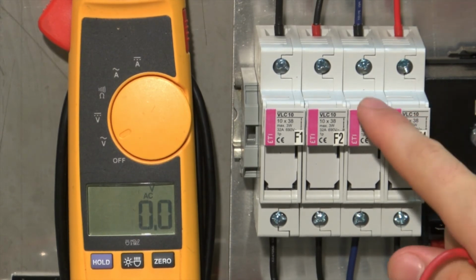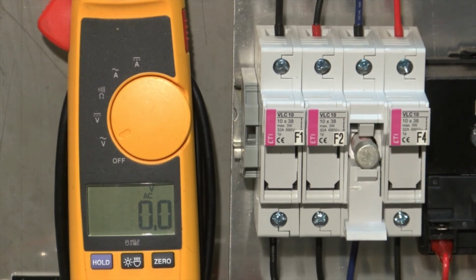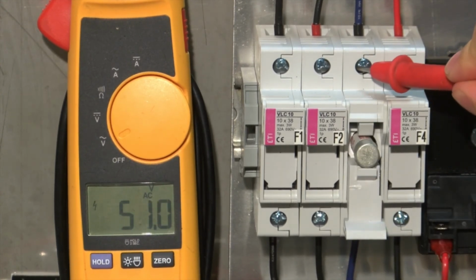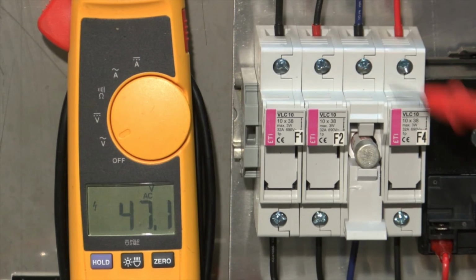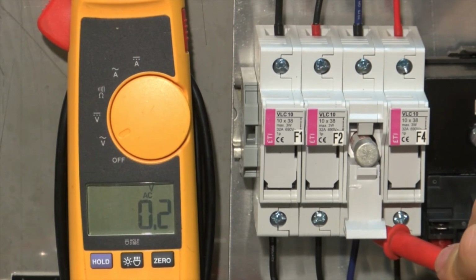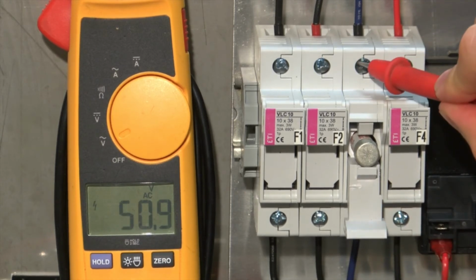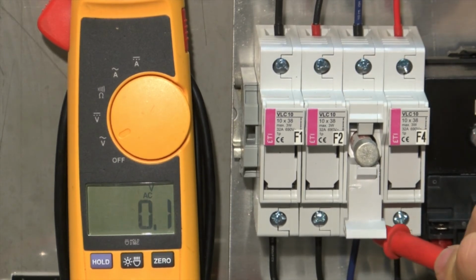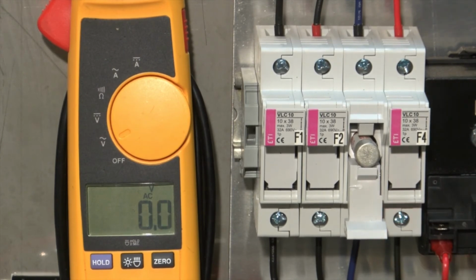In the scenario of a blown fuse, we would see the 48 volts coming in, but no voltage coming out. This would tell you that that fuse is blown. Check the wiring diagram attached to your unit for all fuse ratings. These fuse ratings must be followed for your system to work correctly and be protected safely.